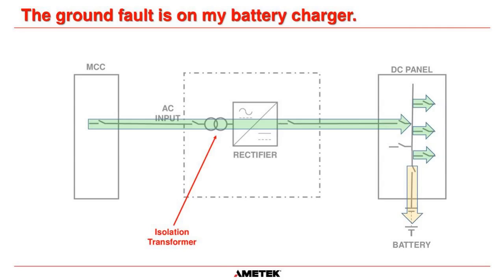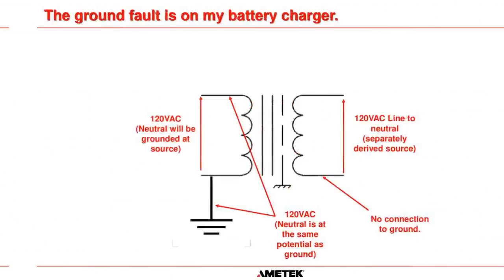So what most charger manufacturers do is they have an isolation transformer at this point here. What that isolation transformer does is give complete galvanic isolation between our AC input and our DC bus, which means the neutral is connected to ground in the MCC, but once we get to the secondary of this transformer, there is absolutely no reference to ground on this circuit, unless it's been intentionally done. Just follow me as we go through these slides and you'll understand more.